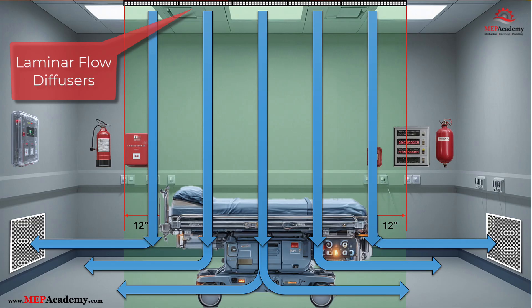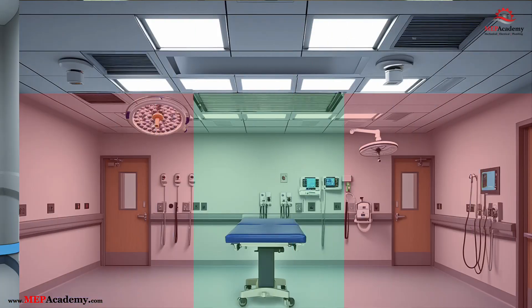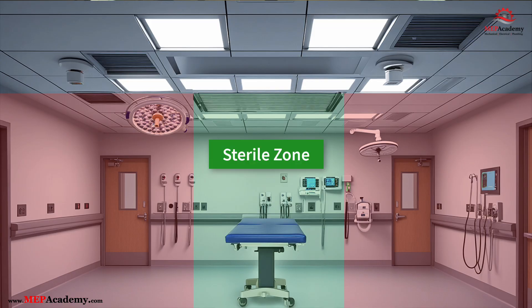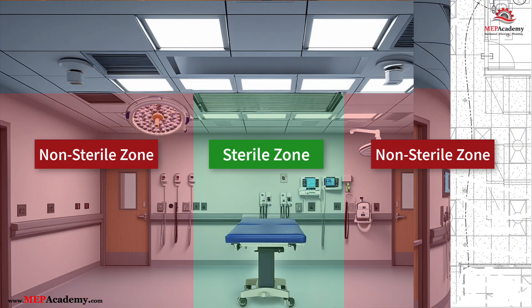This clean filtered air flows straight downward in a smooth column to protect the sterile field. Return air grills are positioned low on the walls, away from the surgical zone, typically at opposite ends of the room, so that air exits after passing over the surgical zone. This design creates a vertical airflow path from ceiling to floor, minimizing turbulence and the spread of contaminants. The area directly above and around the patient is known as the sterile zone, while the outer edges of the room are considered non-sterile zones, and HVAC airflow is engineered to always preserve that boundary.